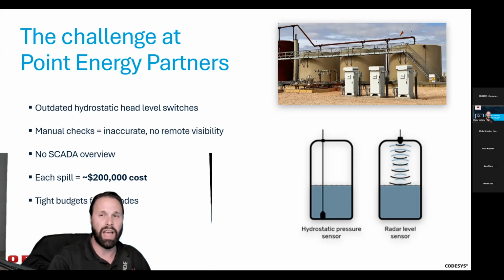Starting out, they didn't have a centralized SCADA system in place for visibility. So if a tank did start creeping toward an unsafe level and those hydrostatic switches weren't working right, they had no way to see that remotely, no alarms to warn them. The risk was real: their own internal studies showed that each time one of those saltwater tanks overflowed, it would cost about $200,000 in lost time and cleanup, not counting environmental consequences and regulatory attention.